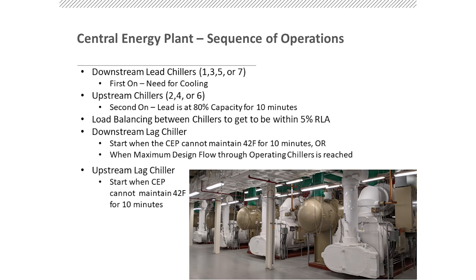Have the sequences up there on the screen. And so with this, there's an upstream and a downstream chiller, right? So obviously, one direction is entering chilled water, the other direction is entering condenser water, and you're going to stage them one at a time. You start with a downstream chiller, which is 1, 3, 5, or 7, and once you have a need for 80% capacity on that chiller, you're going to start your upstream chiller, which is 2, 4, or 6. And I do mean or. They are not paired. You'll see another diagram later on. They can work interchangeably with each one of them.